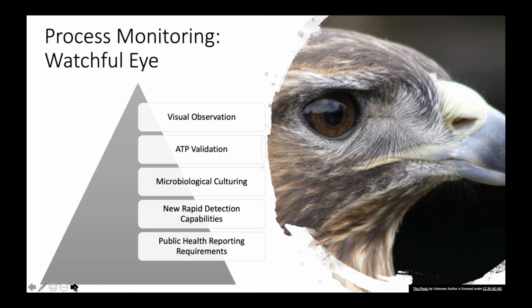Now, if you want to go a step above that, we do have the ability to do microbiological culturing, right? And this is pretty risky because you can have issues with contamination. You need to have an environmental lab, so this should not be done by your hospital lab, preferably. And you're going to see a lot. I've seen at least 3 or 4 rapid technologies that are currently going through the FDA process that will hopefully help us identify breaches more quickly, similar to a biological indicator.